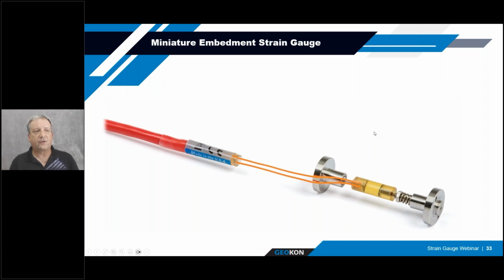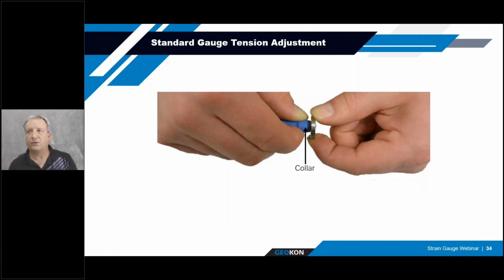On the other end of the spectrum, you've got the small miniature embedment strain gauge, and this is a 2-inch gauge range. It's very similar to the model 4150 with the little coil assembly over the center of the wire tube. On the ends of that 4150, however, you've got the discs that are used for embedment. This type of gauge is typically used in laboratory testing applications, or in zones or areas where you can't fit the standard 6-inch embedment gauge. It's a little bit more delicate, so it's not recommended in most applications, but if you absolutely have to use it, it's available for that use.